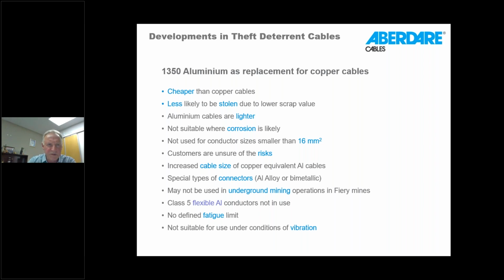So 1350 aluminium as a replacement for copper cables. Aluminium is of course significantly cheaper than copper cables. Aluminium cables are less likely to be stolen due to the lower scrap value. Aluminium cables are lighter. They are not really suitable where corrosion is likely. But having said that, we know that a big utility such as City of Cape Town have been using aluminium for a very, very long time. And even though many of the installations are located close to the sea or subject to a corrosive environment, there are ways of getting around that. So certainly not a showstopper.